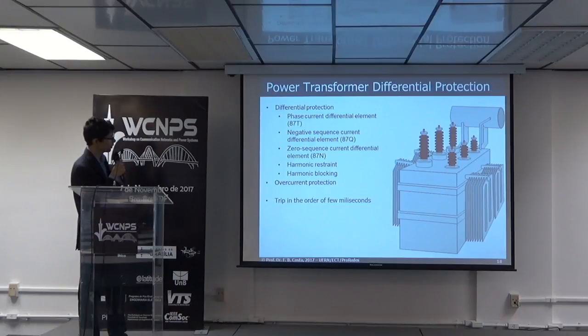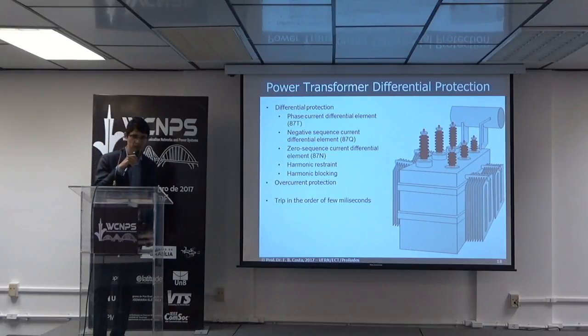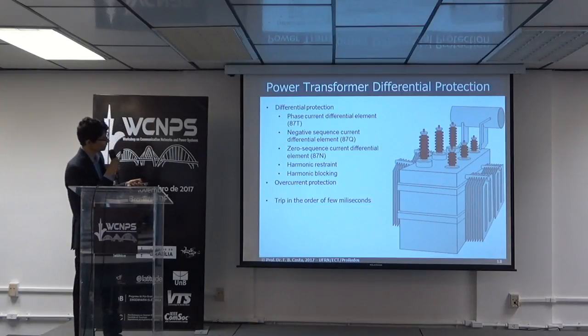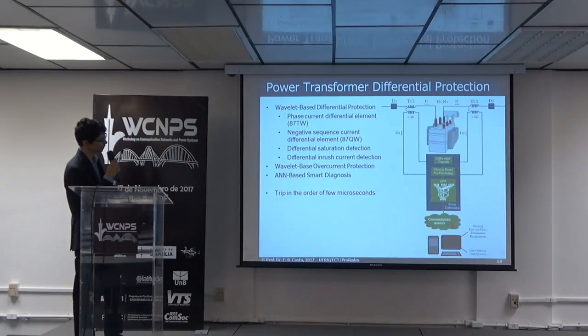Another example is a power transformer whose main protection system is composed of differential protection, as well as other kinds of protection, such as overcurrent protection. However, the trip is in the order of a few milliseconds. By using the Wavelet Transform, this kind of protection could be recreated as wavelet-based differential protection, with similar performance, however, much faster. For instance, here, the trip was reduced to the order of a few microseconds.